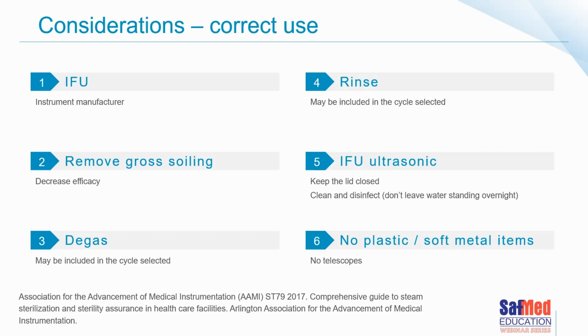While the ultrasonic cleaner is functioning, you need to keep the lid closed. In some of the automated models, if you try open the lid, the cycle will stop. You close the lid, it might then abort the cycle depending on the make and the model of the machine. But the reason for that is to protect you. And there are quite a few published papers around the aerosolization of microorganisms within the CSSD environment if you leave the lid open. Some nice articles around that in the Central Sterilization Journal that I read last month. So please remember to keep the lid closed.